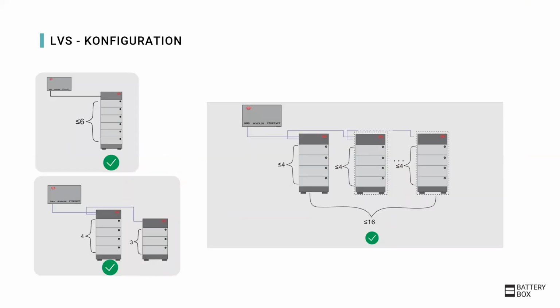As mentioned, up to 6 modules can be connected in one tower. However, this is only the case in a single tower configuration. If multiple towers are connected in parallel, a maximum of 4 modules can be used per tower. Unlike the high voltage systems, in the LVS, towers with different module quantities can also be put in parallel, like shown here for a tower with 4 and with 3 modules. This is possible as the voltage is the same regardless of the module quantity.